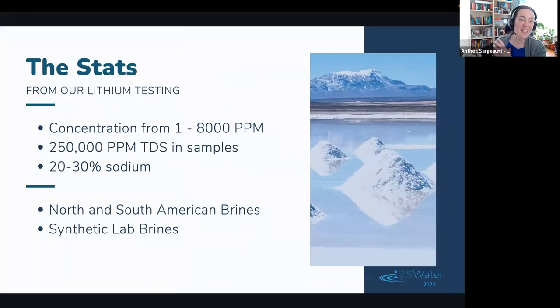And the lithium data that we've got has been really fun, some cool stuff that we've been able to do. We have detected within complicated brines all the way from 1 to over 8,000 parts per million with good accuracy compared to the laboratory. Those samples have been up to 250,000 ppm of TDS, so we've dealt with very high, very complicated matrices and 20 to 30% sodium, as you tend to find in brines.